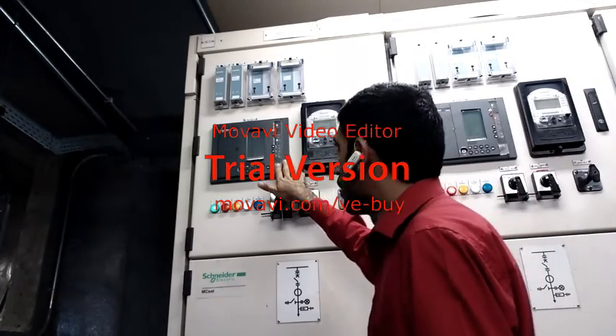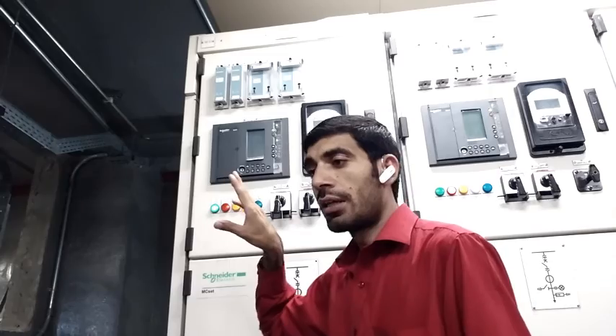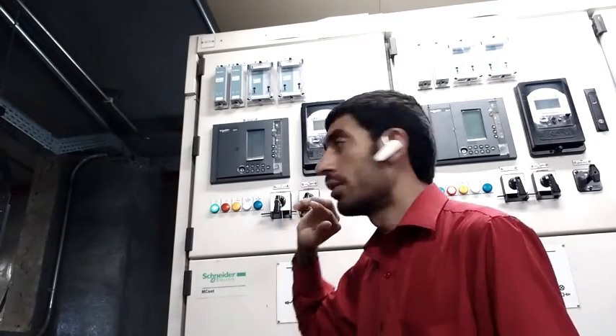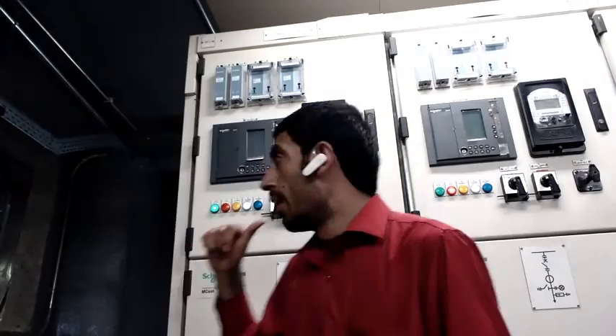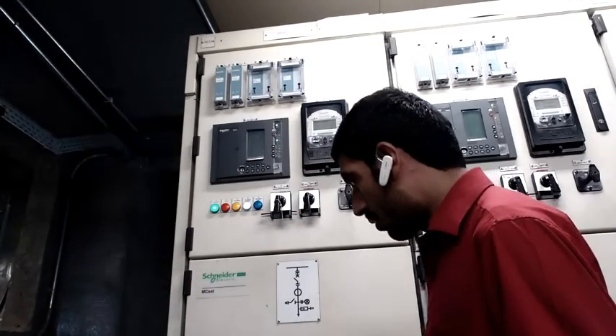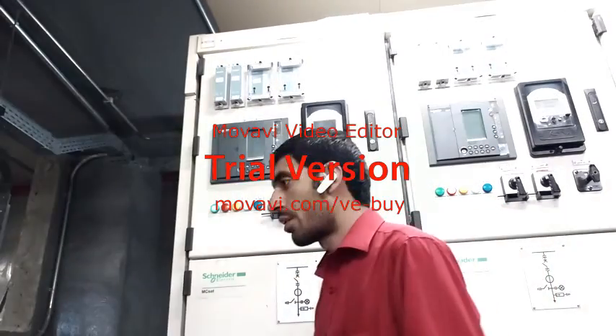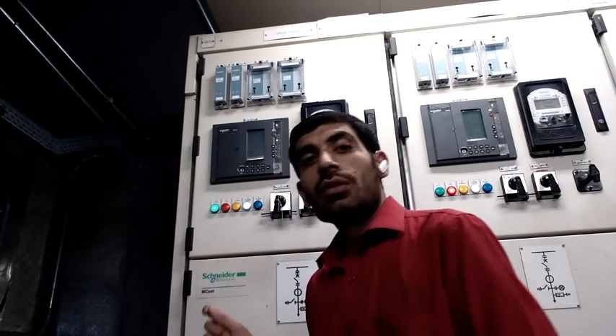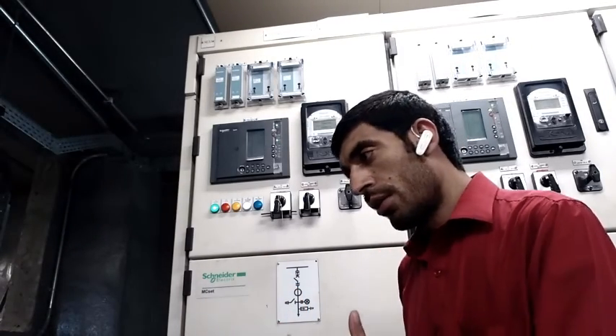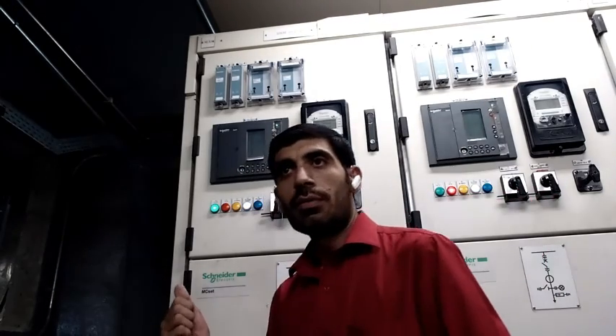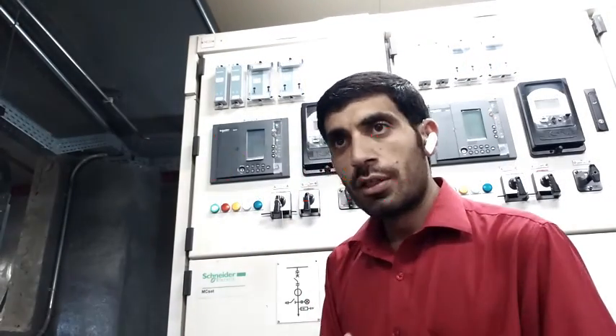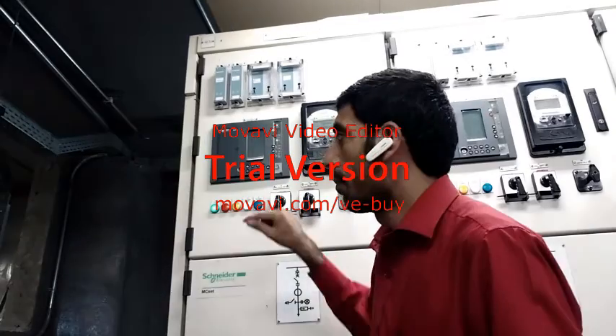So we are giving 3-phase voltage in this relay, and we can see here the value 13.8 kV is phase to phase and 7 point something is phase to neutral. And then how much is our load, we can see also here in this relay, and we put some values in this relay. How much is rated, how much we select as the current value in this relay, how much is our actual value in the system, how much load we are using in our system.